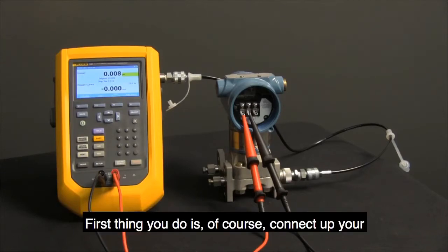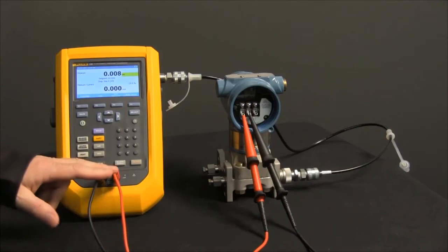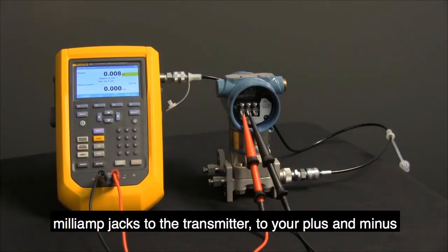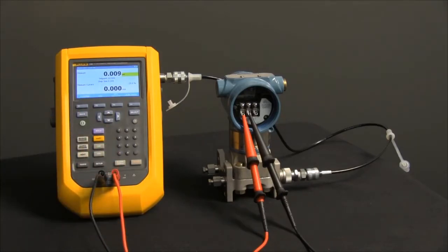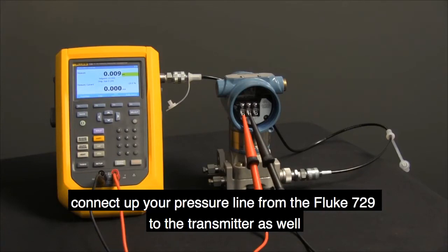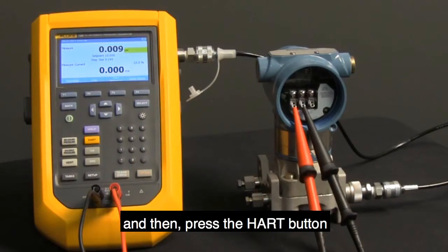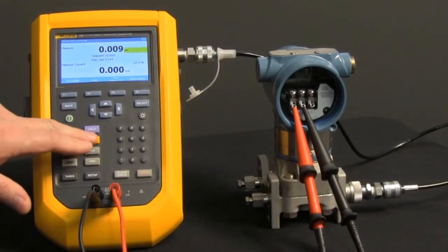First, connect up your milliamp jacks to the transmitter, to your plus and minus. Connect up your pressure line from the Fluke 729 to the transmitter as well. And then press the HART button.